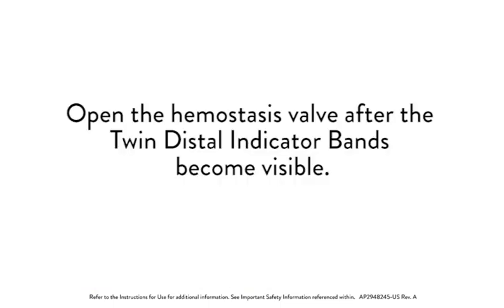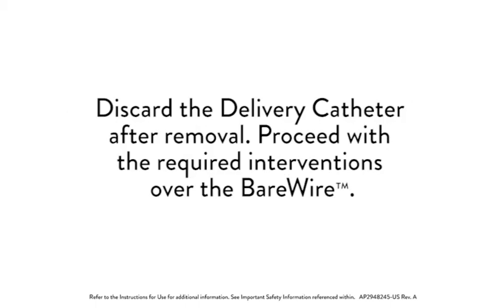Open the hemostasis valve after the twin distal indicator bands become visible. Discard the delivery catheter after removal. Proceed with the required interventions over the BareWire.